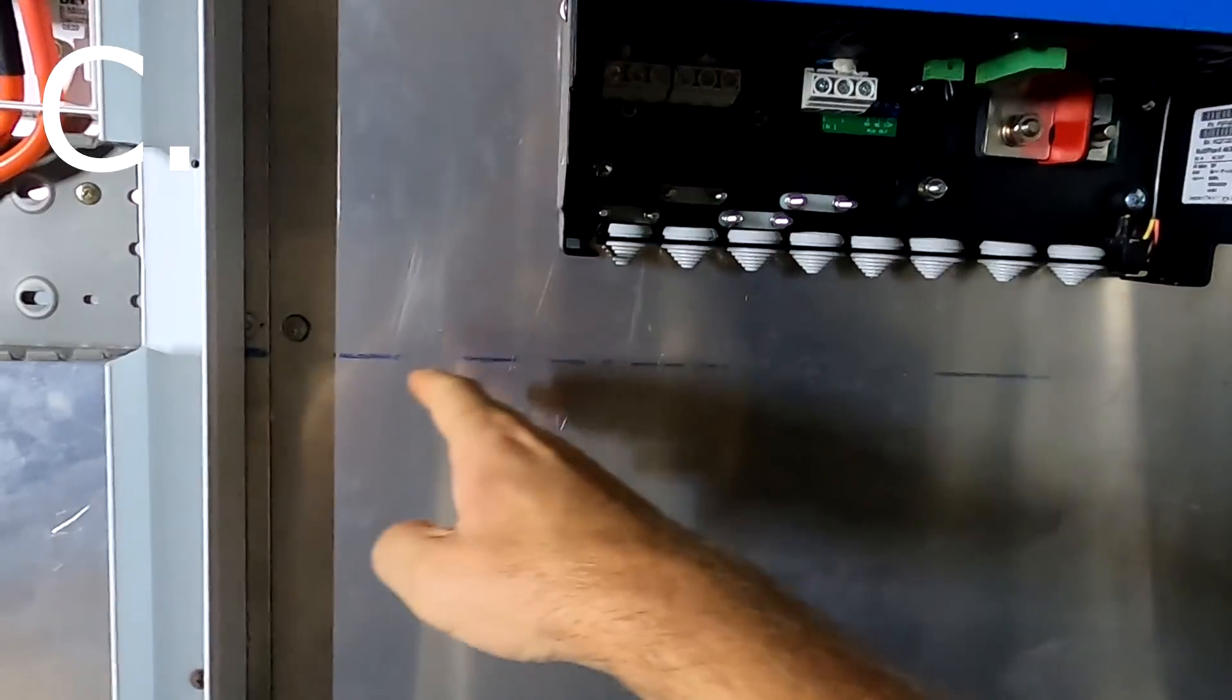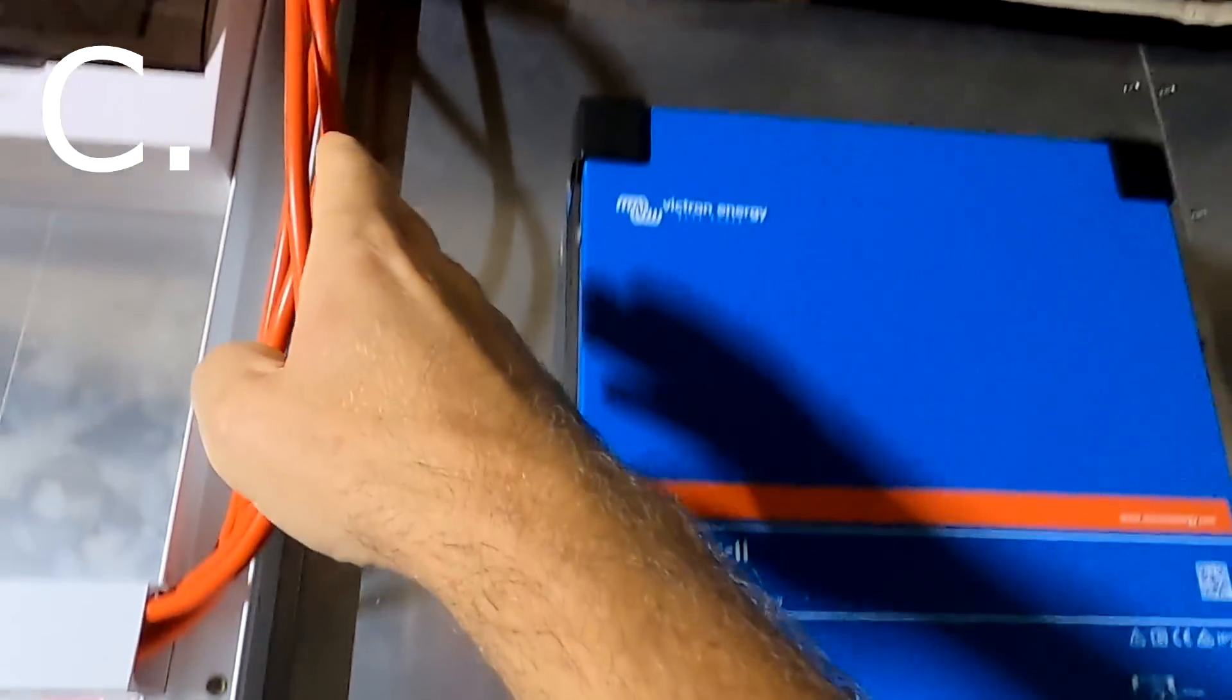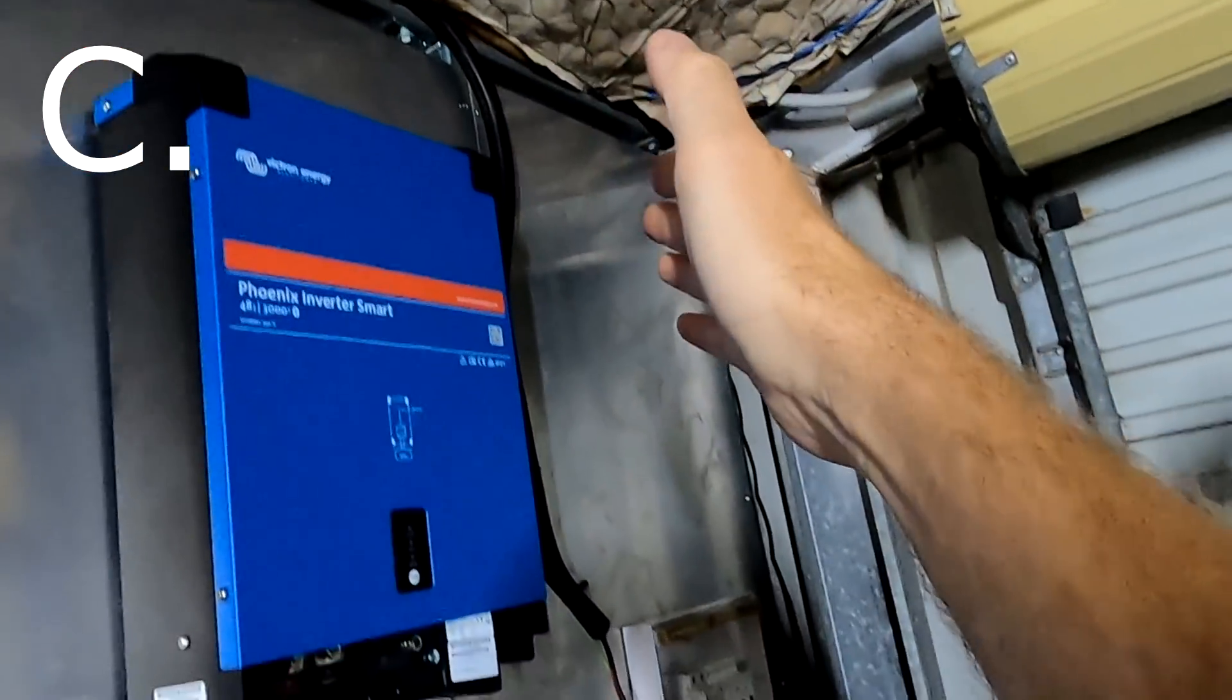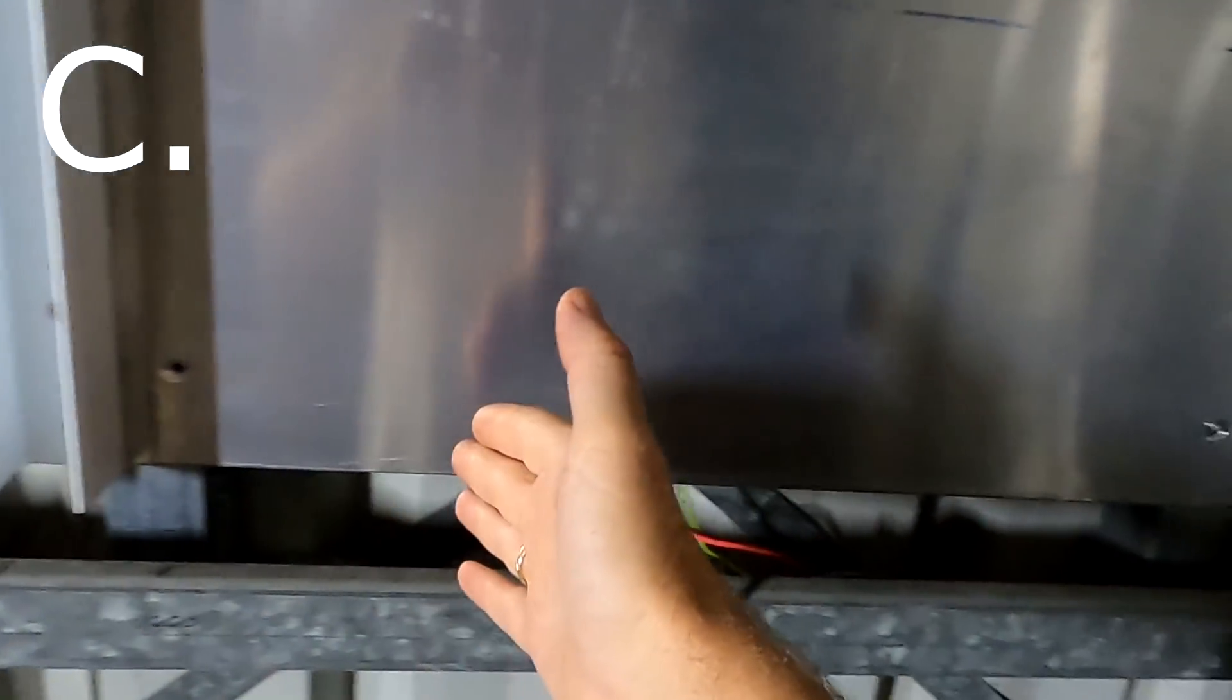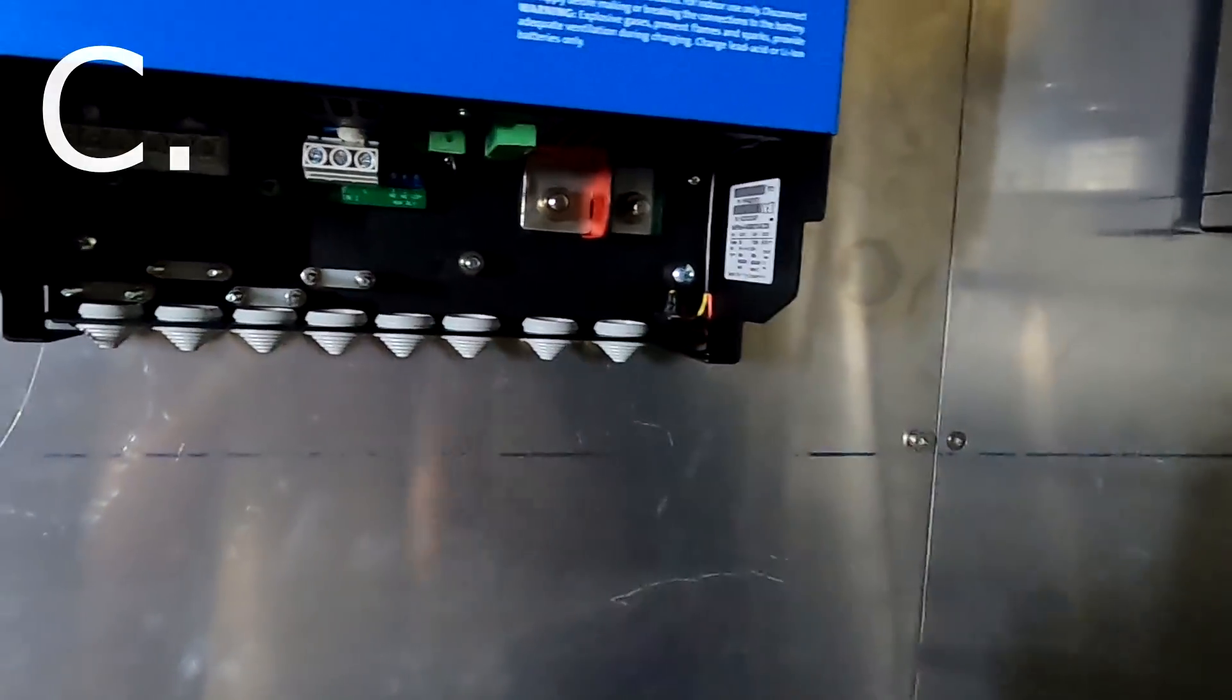This solution with the crossing had about four or five votes. And then of course we had the very popular with 99.99999% of the votes, solution C, where we pull the AC out here and all the way up across there and then coming down from the top to the AC section while we have the DC coming from the bottom here and go all the way up to the inverters. No holes, no crossing but a lot of work because we have to cut all this cable duct. We have longer AC runs. So even solution C seems like the most obvious one because so many people have voted for it and have said, well, I have done exactly the same. AC is coming from the top, DC is coming from the bottom. There's no crossing. They are really separated and there's no confusion. It's clean, easy and as it should be.